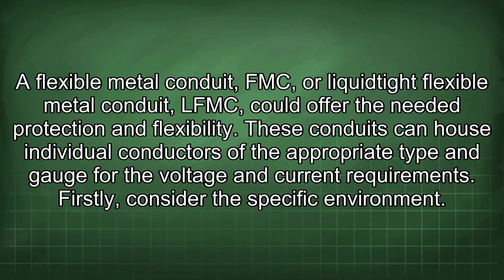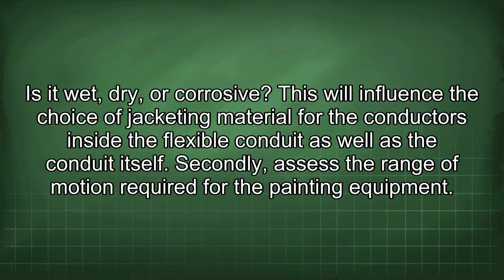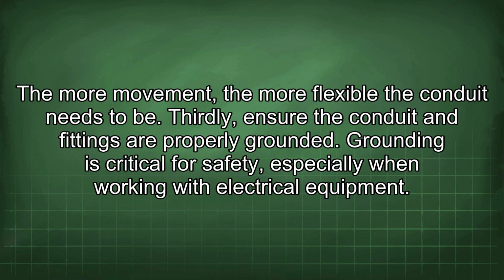Firstly, consider the specific environment. Is it wet, dry, or corrosive? This will influence the choice of jacketing material for the conductors inside the flexible conduit as well as the conduit itself. Secondly, assess the range of motion required for the painting equipment. The more movement, the more flexible the conduit needs to be.